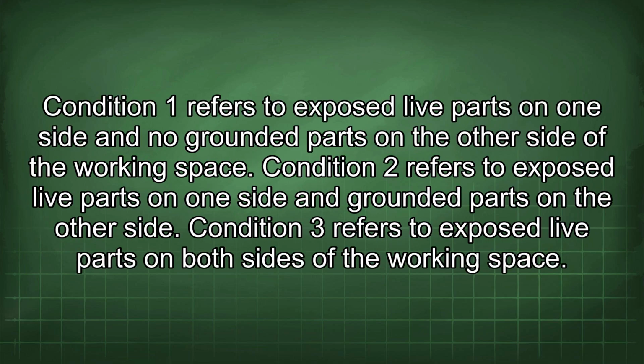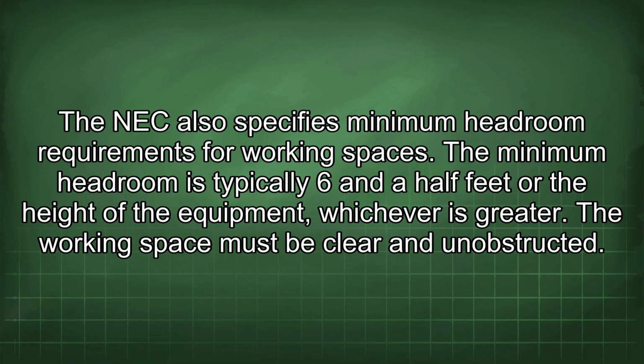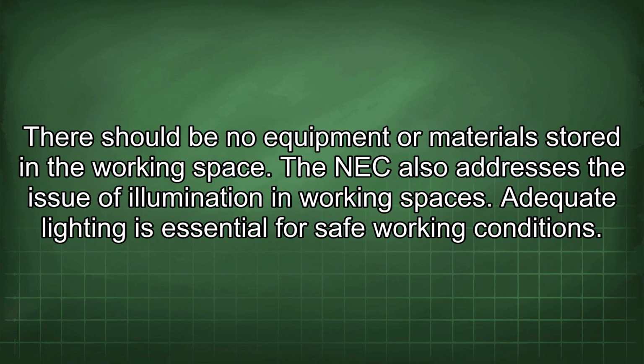Condition 1 refers to exposed live parts on one side and no grounded parts on the other side of the working space. Condition 2 refers to exposed live parts on one side and grounded parts on the other side. Condition 3 refers to exposed live parts on both sides of the working space. The NEC also specifies minimum headroom requirements for working spaces. The minimum headroom is typically 6.5 feet or the height of the equipment, whichever is greater. The working space must be clear and unobstructed. There should be no equipment or materials stored in the working space.